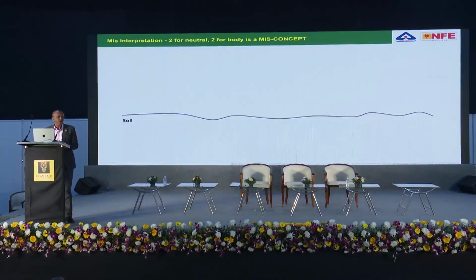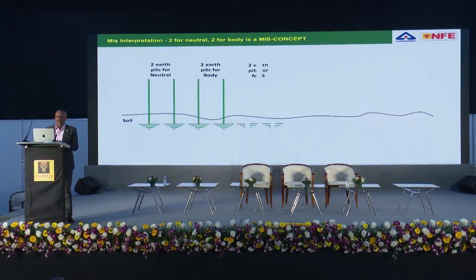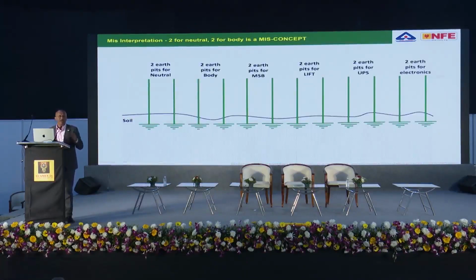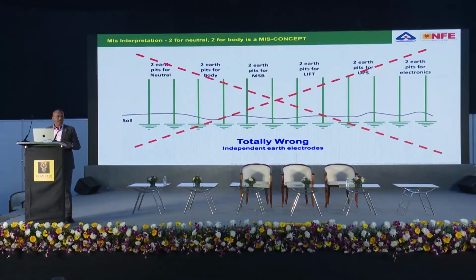But what do we do? Instead of interconnection, we put each and every part of the electrical installation into the earth, because people are confused by the word earth and think that earth means the soil. We put the transformer neutral, two numbers, into soil in a plate, then the body, two numbers, into a GI pipe, and we make hundreds of earth electrodes in soil. Unfortunately, this was never written in any standard or any regulation.